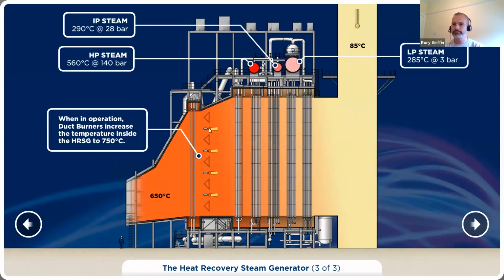We actually have duct burners as well. So we bring these in at the top end to help increase the output of the unit, but they're also quite handy because it helps the unit to provide reserve. So what happens here is the duct burners come in, it fires the gas, and the temperature actually increases to 750 degrees. This increases the temperature and pressure of the steam, so you get higher pressure steam flowing to the steam turbine. The steam turbine is normally about 150 megawatts rated, but it can push up towards 180. So that'll get you 280 on the gas turbine, plus 150 is 430, but with the duct burners, you can get a lift of 20 to 30 megawatts, depending again on ambient conditions.